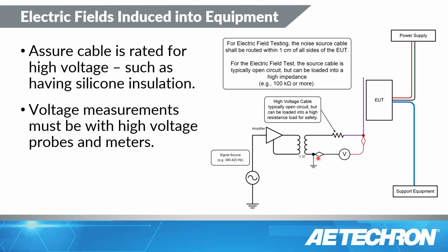And if you're going to use a voltmeter to measure across the transformer, make sure that you're using something that has a high voltage probe, capable of measuring these higher voltages. We don't want to damage something because we're trying to make a measurement across the transformer of a high voltage. So proceed with caution there.